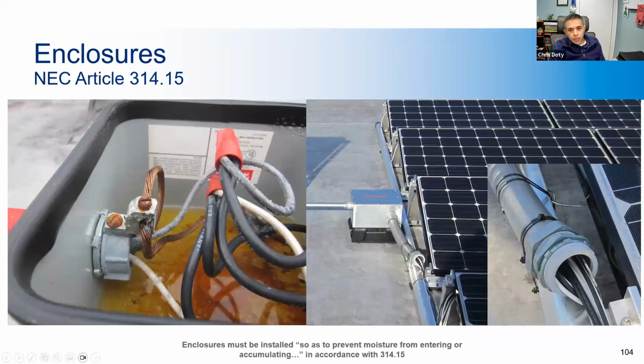All right, here we have an enclosure that's not only suffering from water buildup, as you can see. The lugs on the conduit are not rated for a wet environment. You can see over here, it's rusting. And the wire nut terminations are also not rated for outdoor environment. This is a location that would be well served by the installation of a code compliant weep hole to drain the excess water.